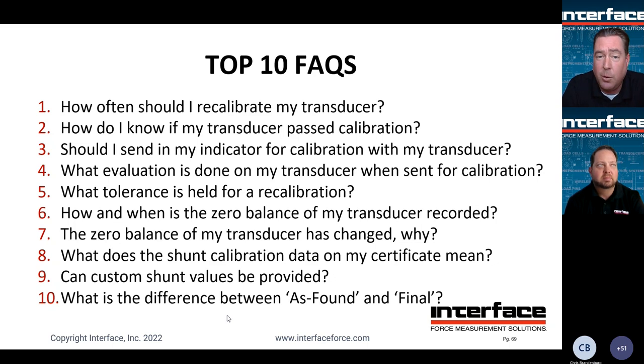As found would indicate that we've received in a load cell and indicator or load cell system that we performed a calibration on and indicated the values that we received in the calibration without any adjustment. So we've not adjusted the instrument, we've not adjusted the load cell. It's exactly how it came in the door.